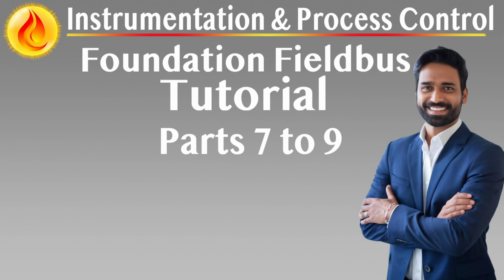Every Foundation Fieldbus device contains at least one VFD, and some complex devices may contain multiple VFDs if they support multiple independent roles or control domains. Each VFD is uniquely addressable and supports consistent access to process variables, parameters, alarms, and configuration settings. The VFD is what host systems and other devices interact with when performing reads, writes, diagnostics, or control operations. This abstraction is critical to maintaining a vendor-neutral, standardized automation infrastructure.